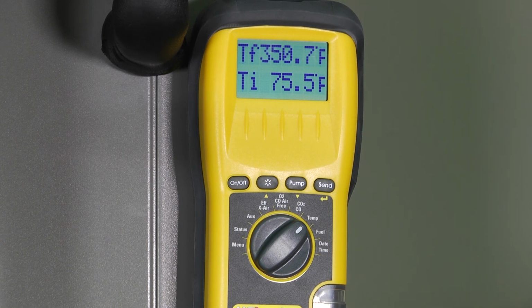I can see that there are no cracks in my heat exchanger because I could watch and see that my excess air didn't go crazy inside of it, and I can see that my carbon monoxide level is well within the standard that I want it to be. So this combustion analyzer is something that every technician should use on every new installation to make sure that brand new piece of equipment is working correctly, and you want to do it on every maintenance because that's what ultimately makes sure you're safely completing your maintenance and understanding what's happening inside that combustion process.